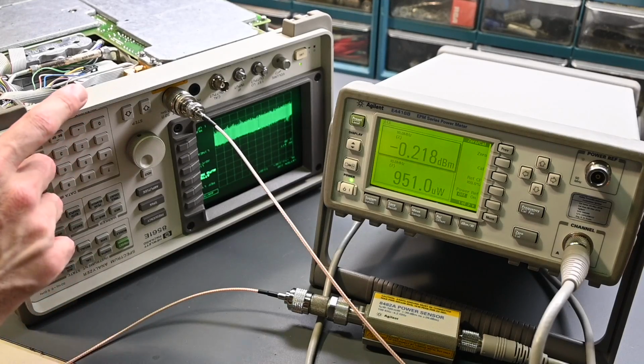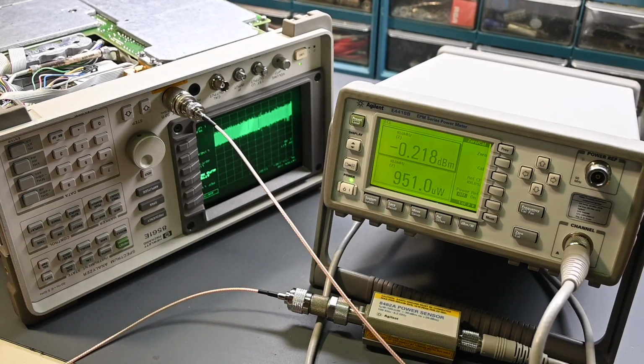The attenuator, again, it steps all the way down to minus 70 dB, but no need to try and take those measurements, because I don't think there's anything wrong with the attenuator at this point. So it looks like some more troubleshooting to take a look at what's next to test, and so let me do some more checking, and we'll continue on.